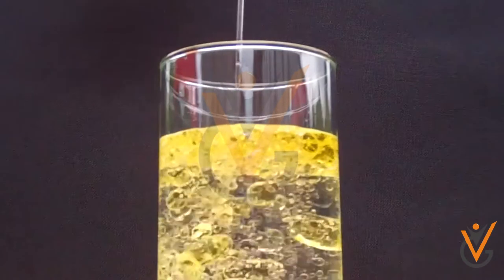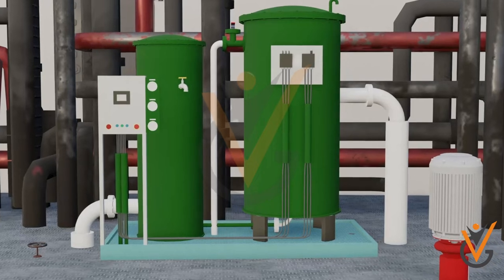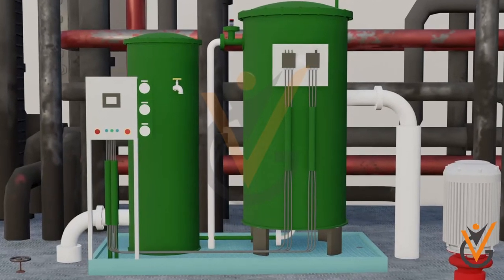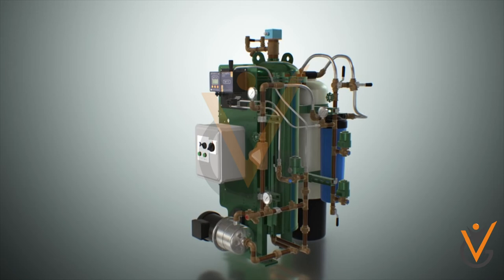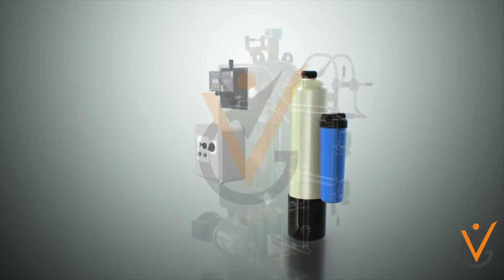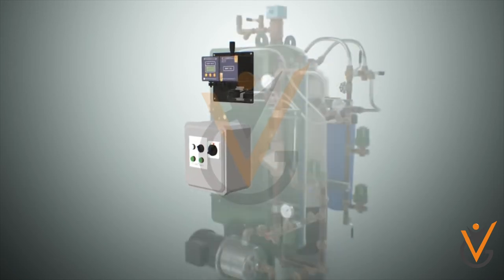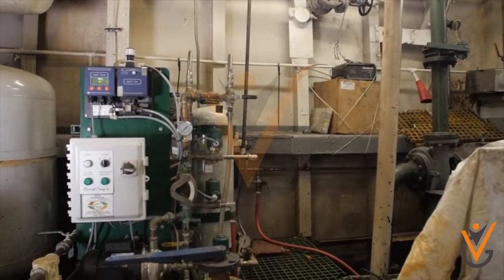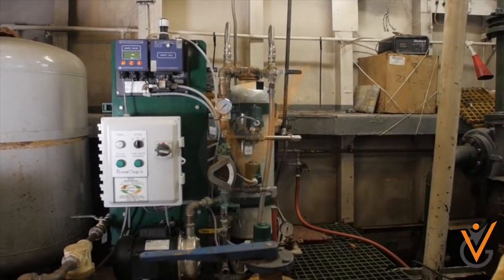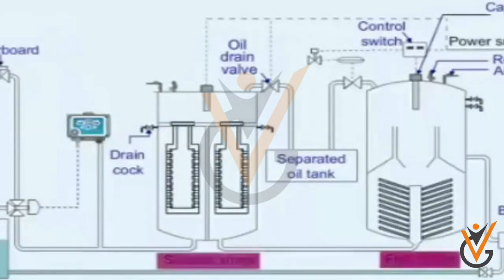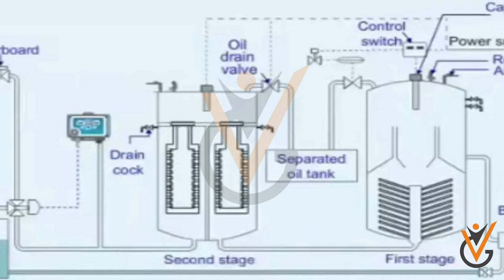The oily water separator works on the principle of gravity differential between oil and water. The construction of an oily water separator is simple, with three main parts: separator, filter, and control unit, with no moving parts. The whole arrangement is separated into two compartments — one for the separator and one for the filter. The complete unit is filled with clean water before operation.